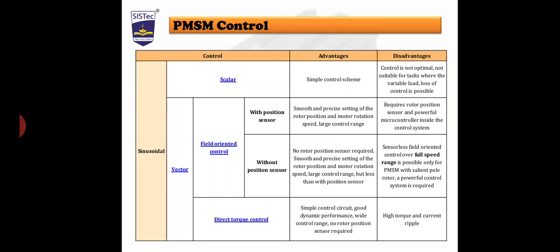Moving on to the second technique: vector control, specifically field oriented control with position sensor. The advantages are smooth and precise settings of the rotor position and motor rotating speed, and a large control range. The drawbacks are that it requires a rotor position sensor and a powerful microcontroller inside the control system, making it costly.